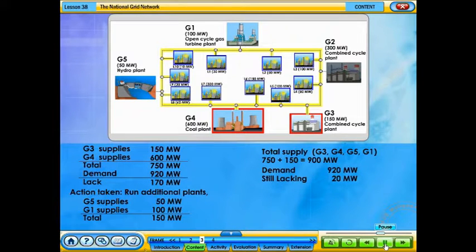The appropriate action is to quickly run the 50 megawatt hydro plant G5 and a 100 megawatt open cycle gas turbine power plant G1, increasing the power supply to the grid to 900 megawatts. However, this is still not sufficient to supply the load of 920 megawatts. As such, at least 20 megawatts of load must be disconnected from the grid in order to balance the mismatch between supply and demand.